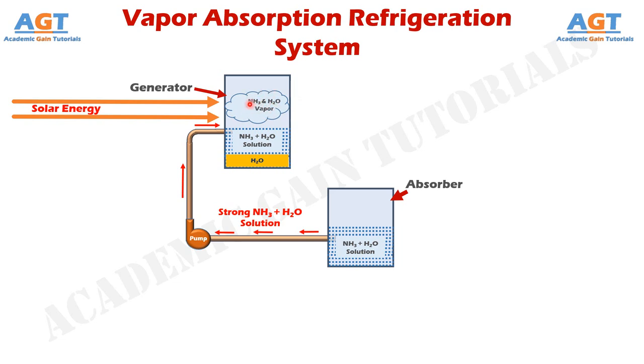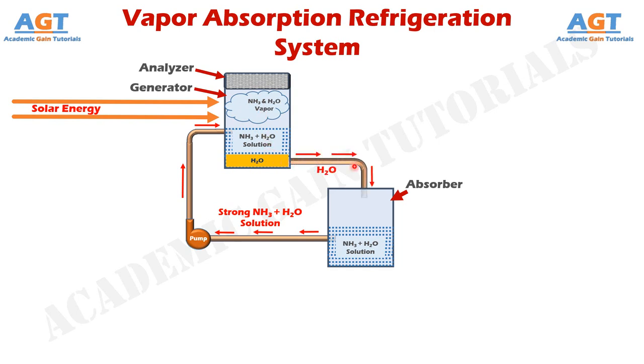We also have an analyzer inside this generator. When this vapor of ammonia and water is passed through this analyzer, the analyzer sends the water vapor back to this generator, and it only lets the ammonia vapor pass through. Then from this generator, the residue of water vapor accumulated here will be passed back to the absorber again through this connecting pipe.